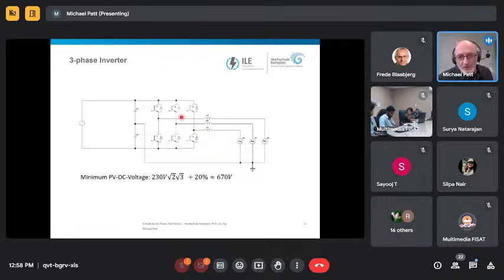But the problem we have here is, since my PV inverter acts like a buck converter, my DC voltage should be more than the voltage here. This voltage is 230 by root of 2 by root of 3, because of the three phase, plus again the 20%. We are at 670 volt. Below 670 volt, it will not work.